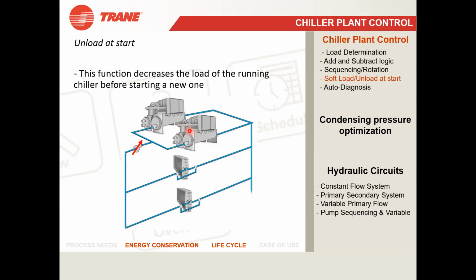In this context, I want to mention, I know you all know, that every chiller is designed to run at minimum flow. So when the first chiller is working and gets a signal from the controller or from the CPC that we are switching on another chiller, it will reduce to the minimum percentage of load at which it can operate. So maybe 15 to 20% load, and then it will start another chiller, and then gradually both will be loaded.